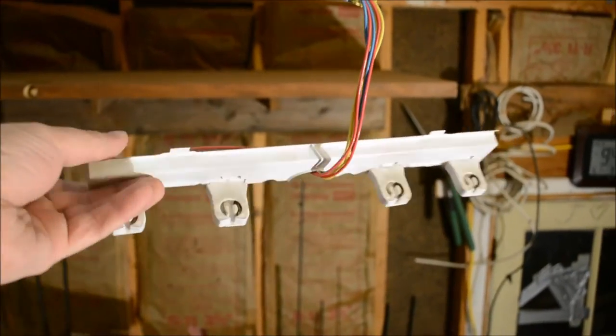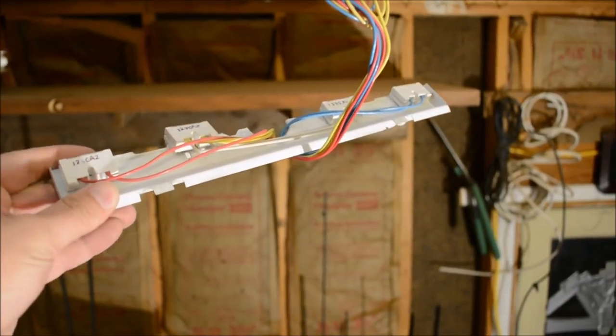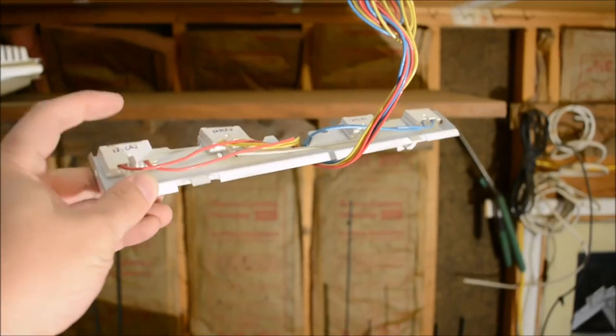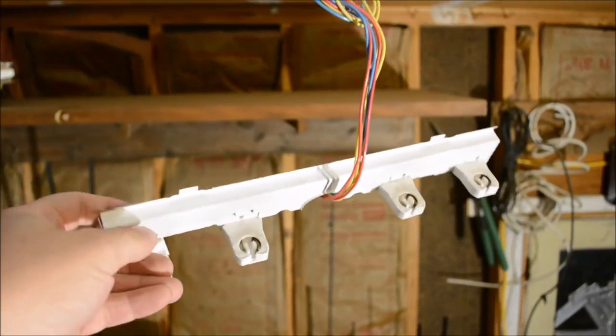So once you have it down, you look at the wires and trace it to the ballast. That's bad. Since it's the outer set, that's bad. I trace those wires up to the first ballast.